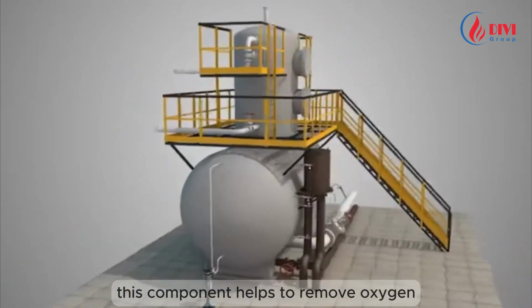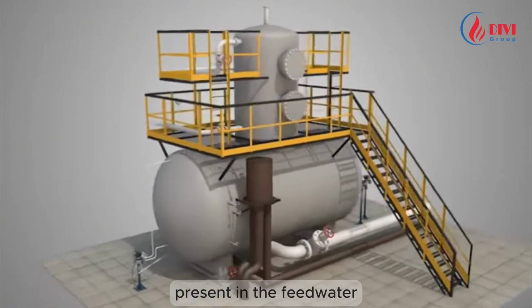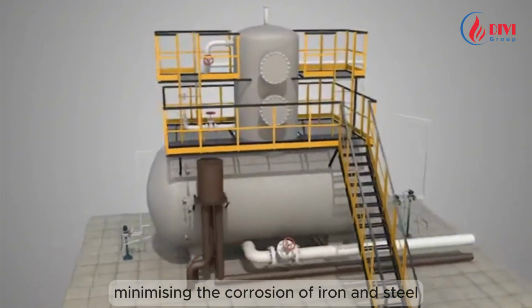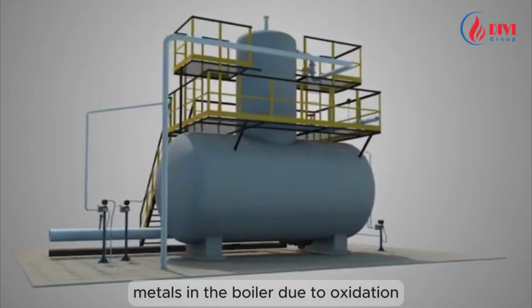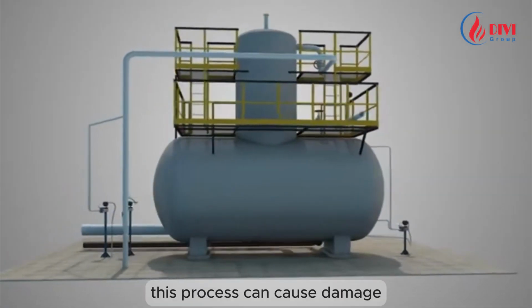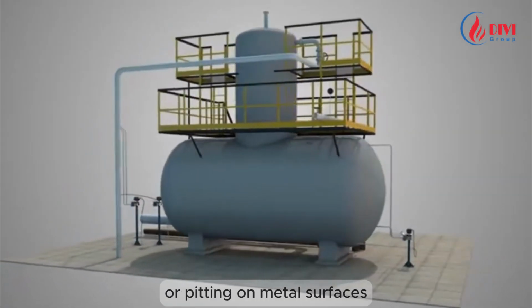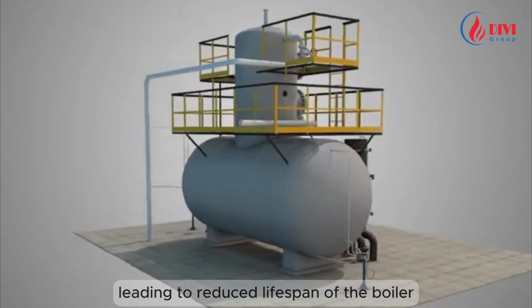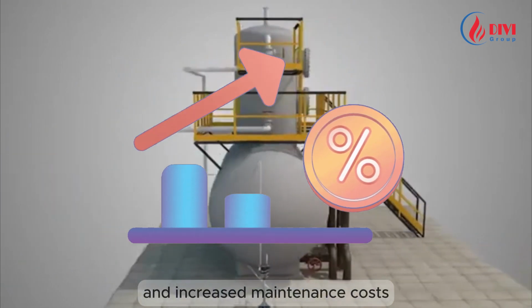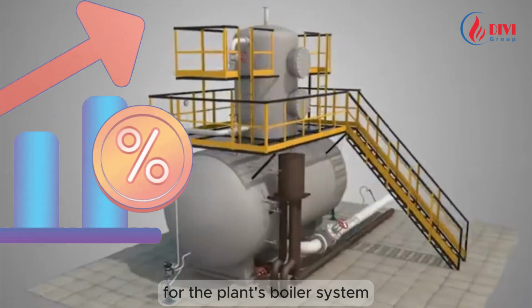As we know, in the industrial boiler system, the Deaerator tank plays a particularly important role. This component helps to remove oxygen present in the feed water, minimizing the corrosion of iron and steel metals in the boiler due to oxidation. This process can cause damage or pitting on metal surfaces, leading to reduced lifespan of the boiler and increased maintenance costs for the plant's boiler system.